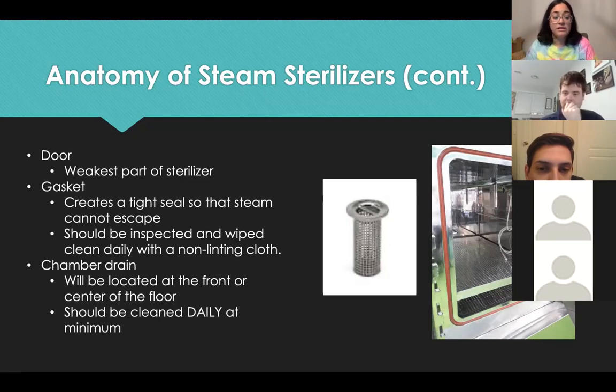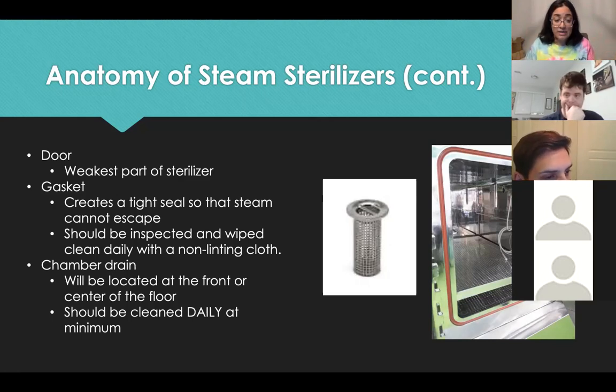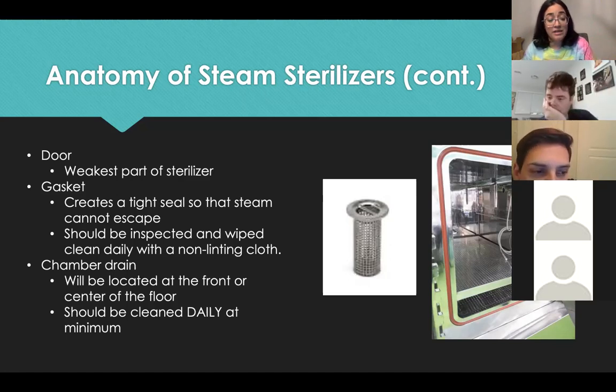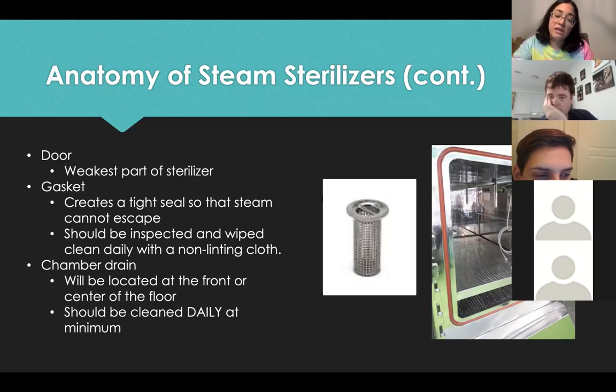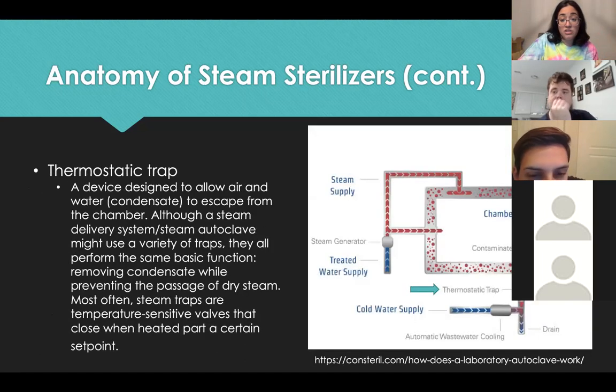The gasket is the rubber seal that forms a tight seal in the sterilizer so steam doesn't escape. If the gasket is damaged, it can interfere with sterilization cycles — so gaskets must be inspected daily and cleaned with a non-linting cloth. The chamber drain is located toward the front or center of the floor and must be cleaned daily; if it gets clogged, it can cause major issues for sterilization.